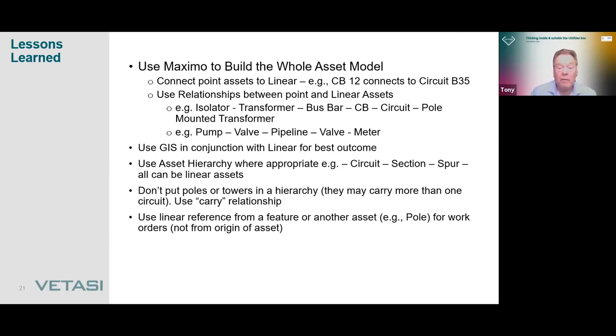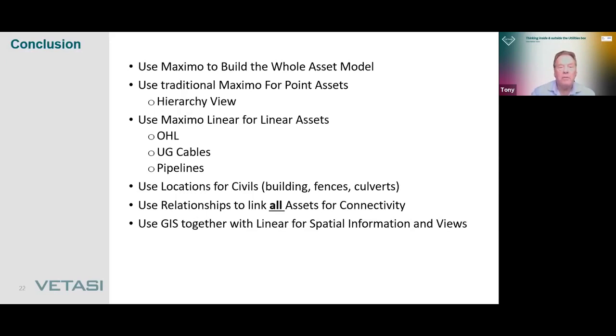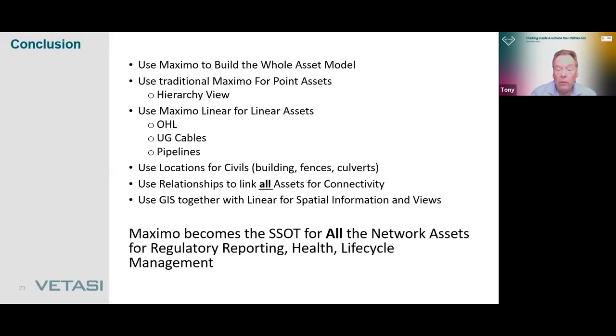Conclusion: Use Maximo to build the whole asset model. Use traditional Maximo for point assets. Use Maximo linear to represent linear assets such as overhead lines, underground cables, and pipelines. Use locations for civils where there may not be an asset, such as fences, buildings, culverts. Use relationships to link all assets for connectivity and to show things like carrying — the pole carries, or the building contains. Use GIS together with linear for spatial information. Basically, Maximo becomes a single source of truth for all network assets and work management, regulatory reporting, asset health, and lifecycle management. That concludes the presentation — thank you for listening.